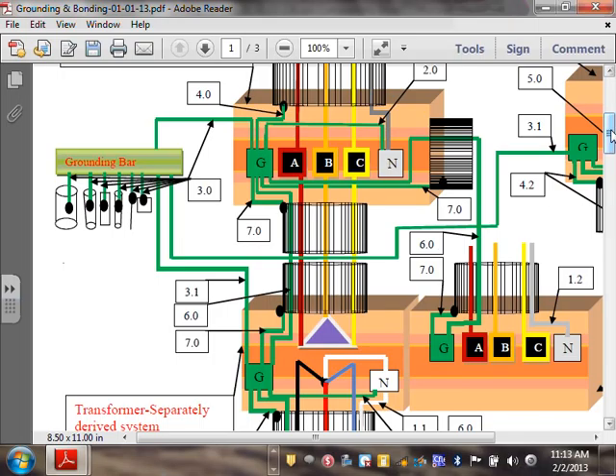Another time you create a separate derived system is if you have a generator. If you have a generator, now I generate 3-phase. If I need a second voltage, typically we need 480, but I need a 277, so you create a neutral. Now we create a neutral. When you create a neutral in a generator, you have an option though. You can tie your neutral that you created to the service and call it a day. That will be a non-separate derived system. The other method is I want to break the two neutrals from each other, break them, and then that will be a separate derived system. And we'll talk about the advantage and disadvantage when we reach them.